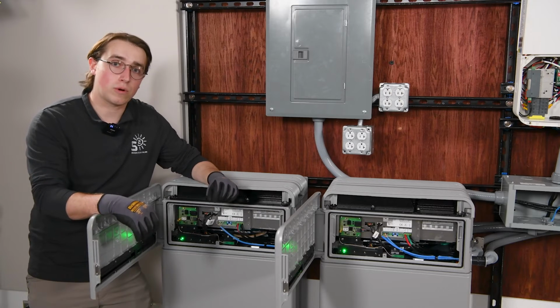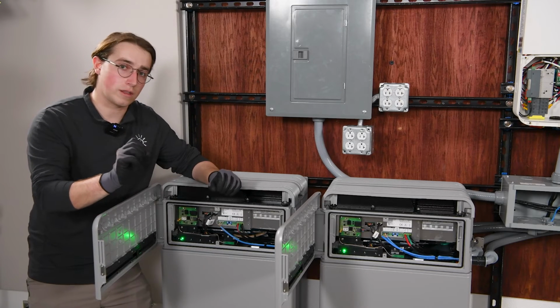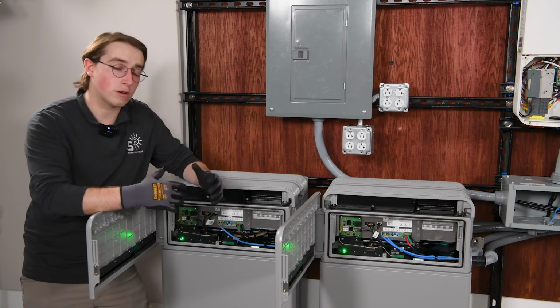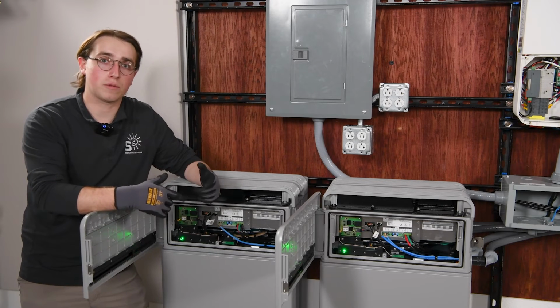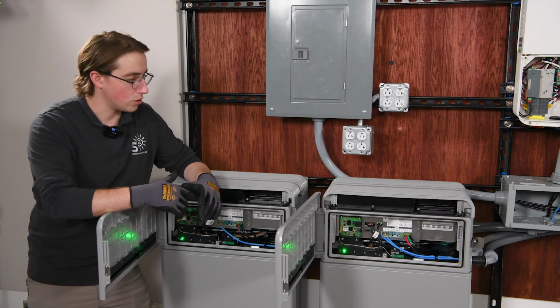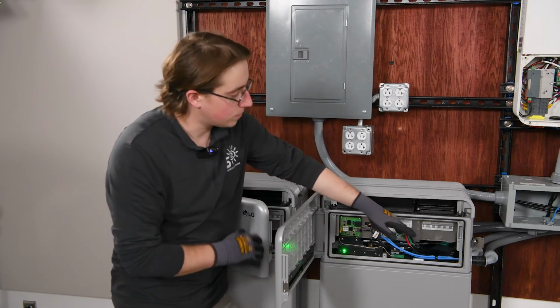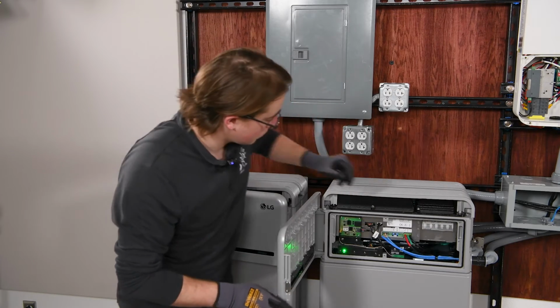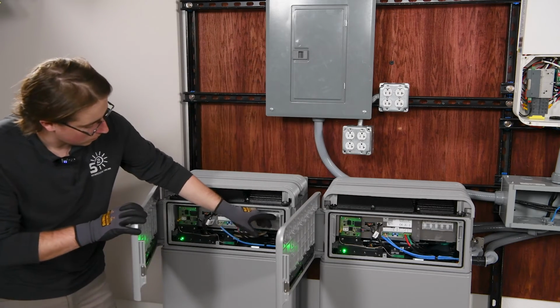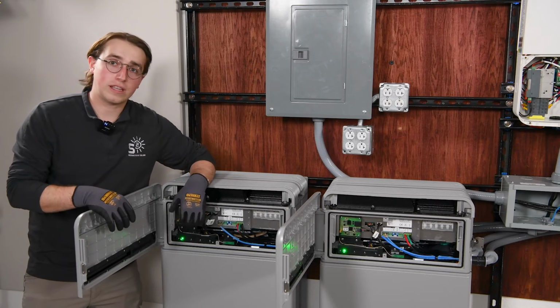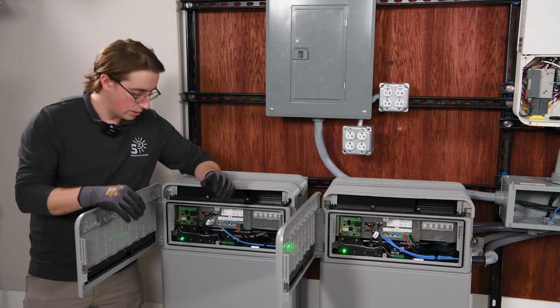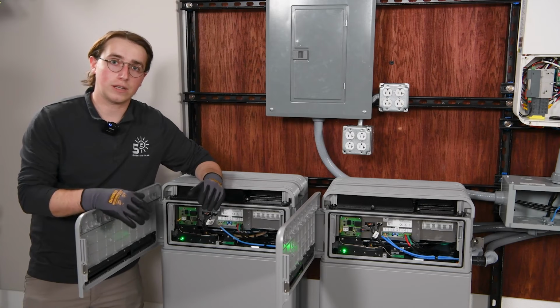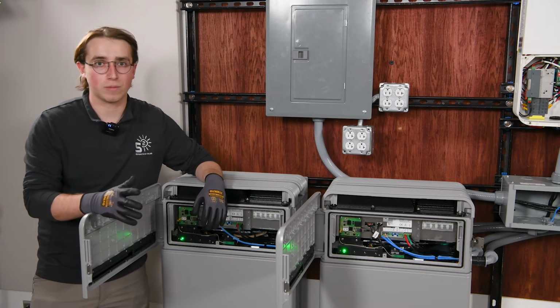If the green light is pulsing slowly, where it's on and then off, on and off, then they're in standby mode and we'll need to power cycle the batteries to wake them back up. To do that, we'll just turn the batteries off. We'll make sure that the LED lights turn off completely, and then once they're turned off completely, we can power the batteries back up and that will complete the cycle.